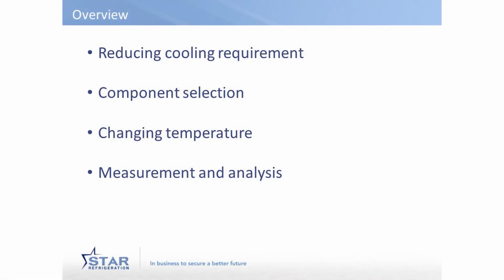spend point of view. And it's amazing the amount of refrigeration systems that are running, but they're not actually contributing anything beneficial to the flow process, whether that's cold storage or whiskey bottling or cheese production or whatever. The system is running, but it really ought not be running. And as a contractor, I shouldn't be saying to you, make your refrigeration system smaller, but it's definitely the best way to save energy is by right-sizing the system.